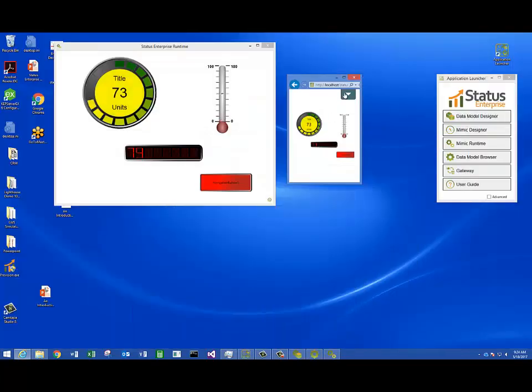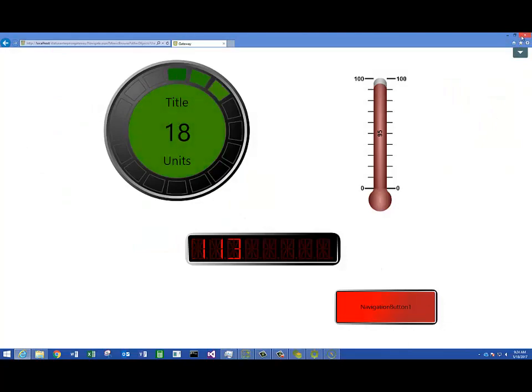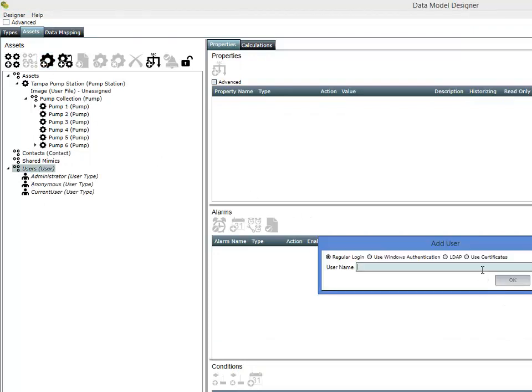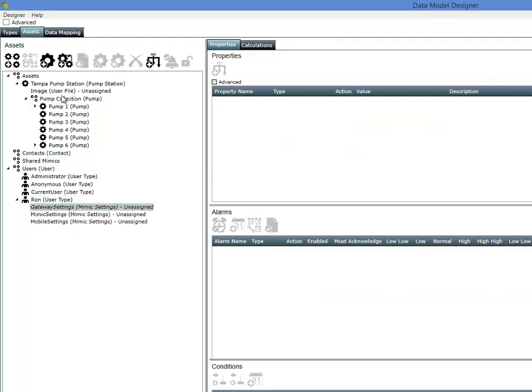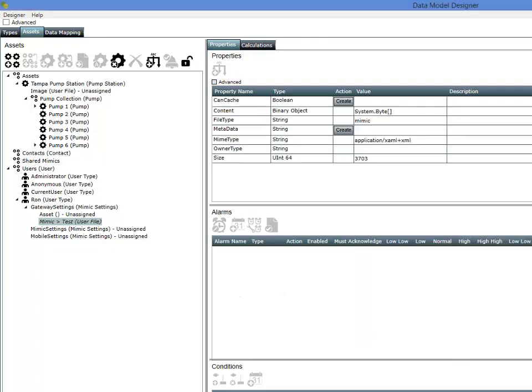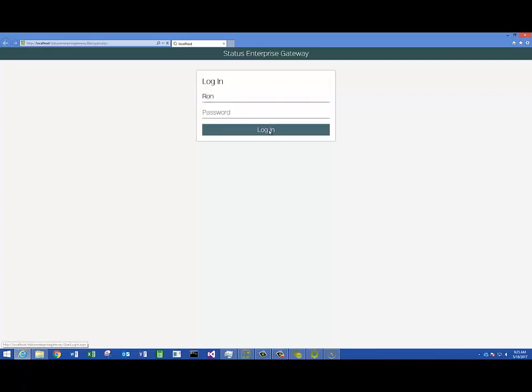When I navigated into the web browser, I had to log in and navigate down to the screen I want. Maybe I'd like the user to be automatically taken to a screen. Going back to the Model Designer under Assets, I have Users here, and I can create a new user — here's Ron. We can use different types of authentication for Ron: LDAP, X.509 certificates, Windows authentication, or regular username and password. I can go to Ron's settings and specify which screen Ron is going to see when he logs in — I can say he's going to be taken directly to Test. Going back to the web gateway, logging in as Ron, Ron goes directly to his screen now.